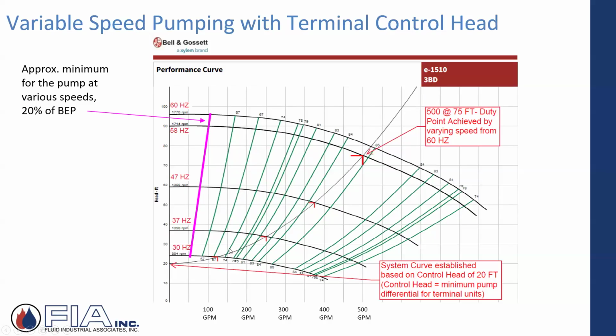So variable speed pumping with terminal control head. So design conditions maybe are saying, look, at 500 gallons a minute, 75 feet, duty point. System curve, though, if you notice, isn't starting at 0. It's jumped up. I have a system curve established based on a control head of 20 feet, the minimum pump differential for the terminal units. I build that in. I've selected that. That's that control valve capability.